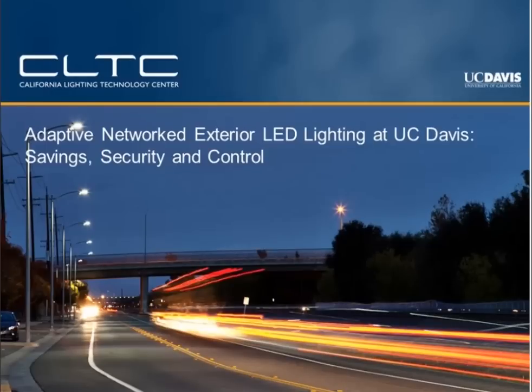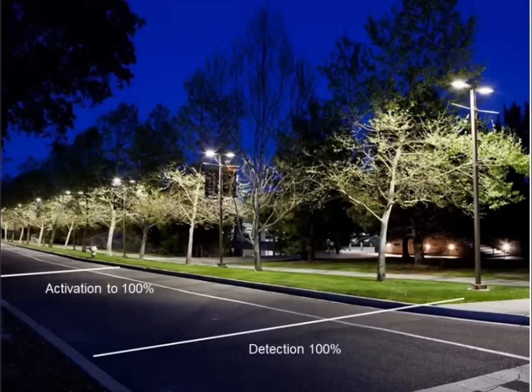Now we're using a lot of this pathway lighting to help inform some of the street lighting applications, where we use this kind of sibling control, where we make decisions at one place and then broadcast the signal down. We're looking at this with the idea that it could help inform some of the activities, and we're working with the City of Davis now on this networked control system. The idea is that we detect motion, either a pedestrian, bicycle, car, or motorcycle, and then it sends signals down to siblings to come up to 100%. We've had a lot of success with this on different roadways. Again, the light's at 50%, we then RF to bring everything else up to 100. So this has been quite successful.